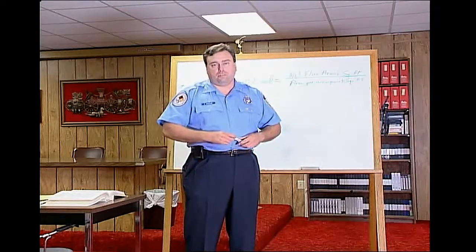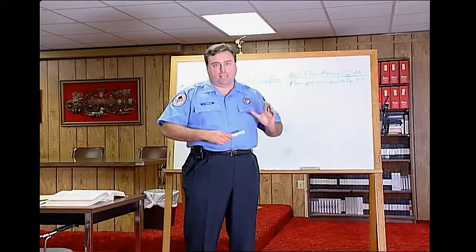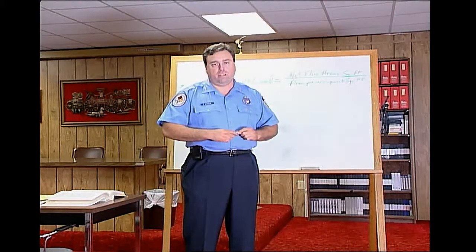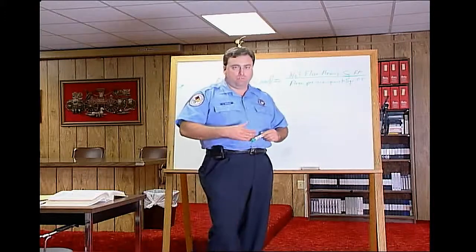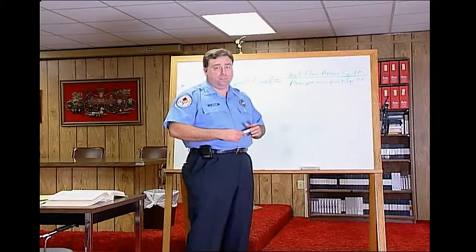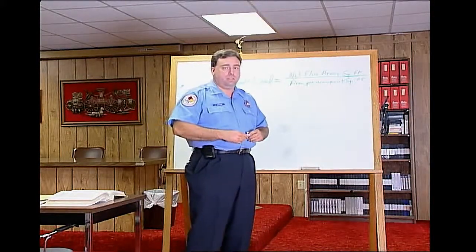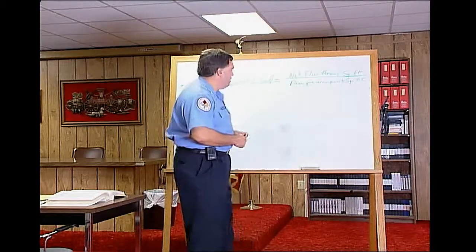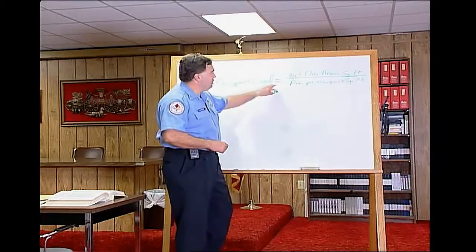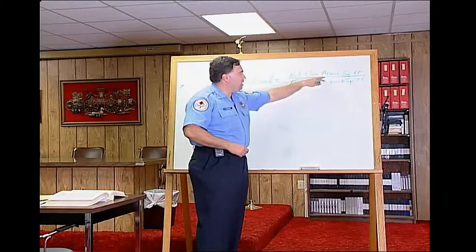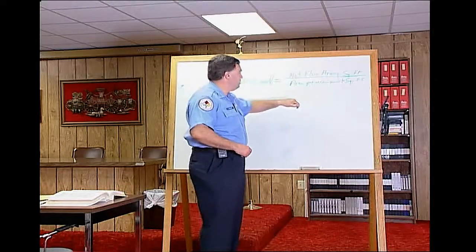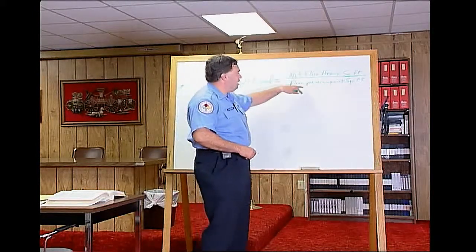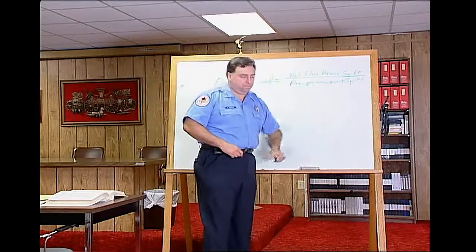The next time you go into your favorite restaurant, you might notice a sign that has the occupancy on it. We're going to show you the formula they use in order to come up with the number of people that should be in that particular area. Your occupancy load will equal your net floor area, square foot, divided by the area per occupant per square foot.